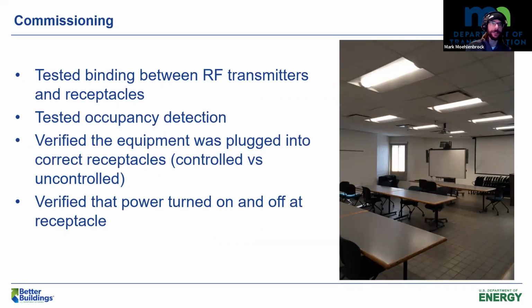Okay, so the commissioning process tested the binding between the RF transmitters and the receptacles, just to make sure that it was bound to the correct receptacles. Tested the occupancy detection. What I basically did to do this, it was kind of low tech. As it were, this project was being commissioned about the time the first wave of COVID was happening, and the pre-commissioning agent was located in Las Vegas. So I had to do a lot of this myself when I normally wouldn't. So I got to be a little bit more intimately familiar with it than I really wanted to be.